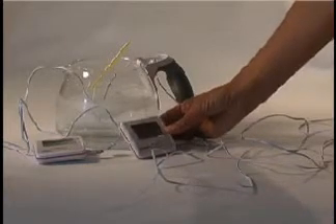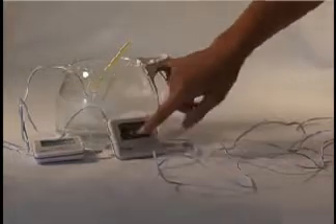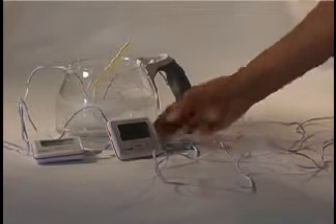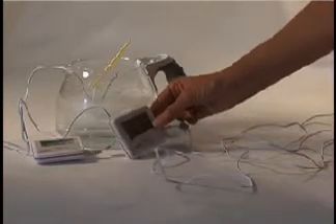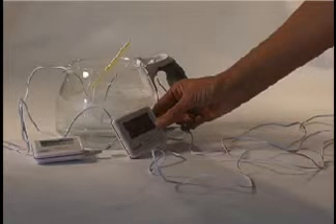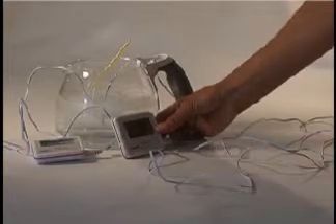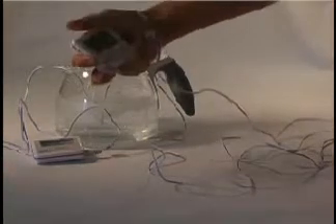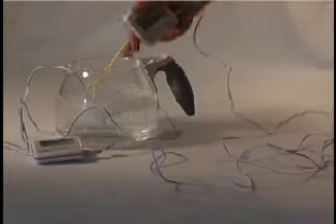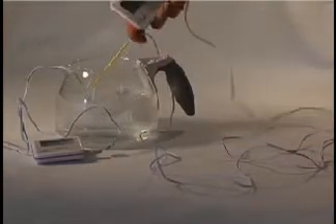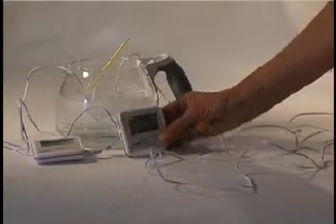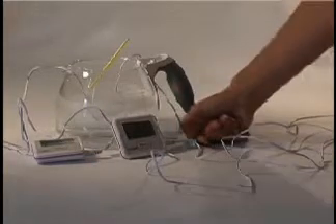So in terms of instrumentation error, which is one of the components of imprecision, you've got the uncertainty in the display, how you read it. And that can be important. For example, if you always read your temperature probe, you know you're a certain height, you read it one way, and it's going to be really repeatable every time you read it. But if you've got different people, sometimes the other person takes it down, looks at it, maybe they hold it for a while. Does that change the temperature? Does that change something in terms of where the actual probe is? So when you've got different people operating your instruments, the instrumentation error can be increased.